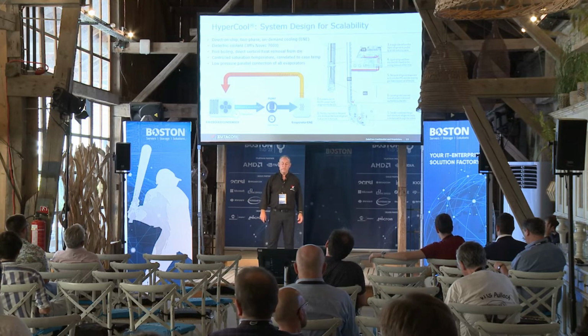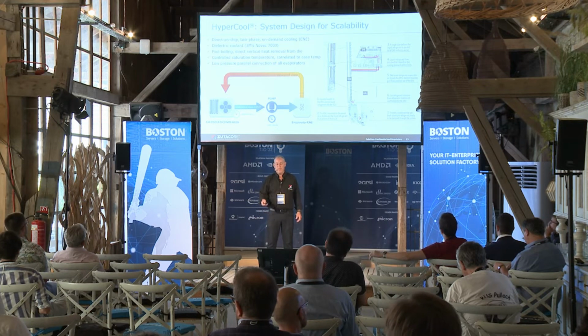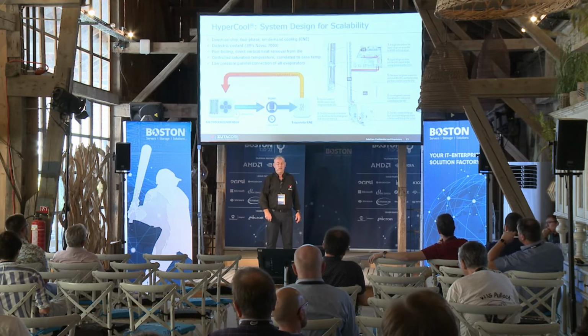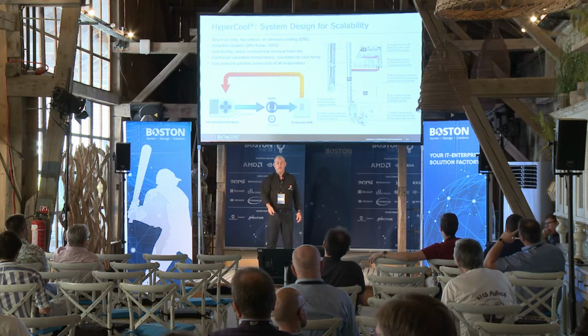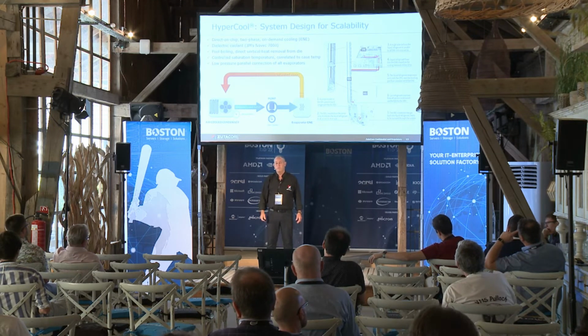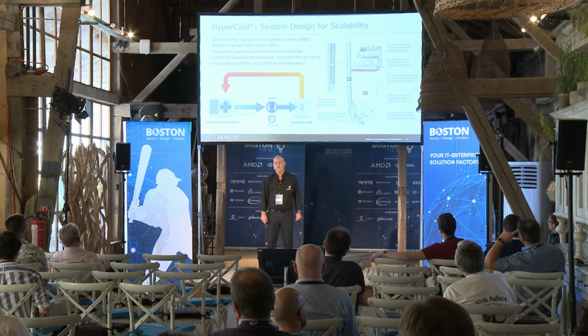So how does the system look? What you see on the right side, condenser at the bottom of the rack, and you can see a demo there in the lobby. Servers are all over the rack. You have a manifold, a very simple aluminum manifold on the side of the rack, just about the same size as the PDU, the power distribution unit. And every server is connected by 2 tubes into this manifold.